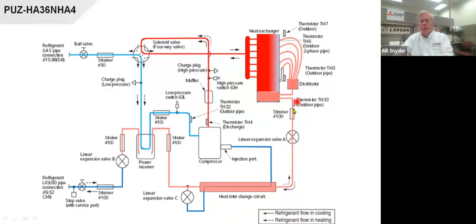There's a thermistor right here and a thermistor right here. Linear expansion valve, strainer, go through that heat exchanger circuit, another strainer. This is the power receiver, because we're running a liquid line through this, plus we have a dip from our suction line. So we're doing some heat transfer here, we're doing heat transfer here, and we're driving this compressor to a high speed so that we get as much heat out of it as possible.